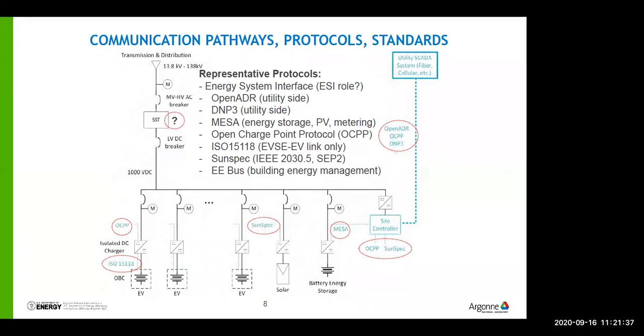We have low voltage DC breakers running at that 1,000 to 2,000 volt distribution, and then the equivalent of a bus bar. This is called DC as a service, where the utility would own the equipment, and that line of demarcation isn't where the medium or low voltage connection is—it's actually at the point here where it says 1,000 volts DC.